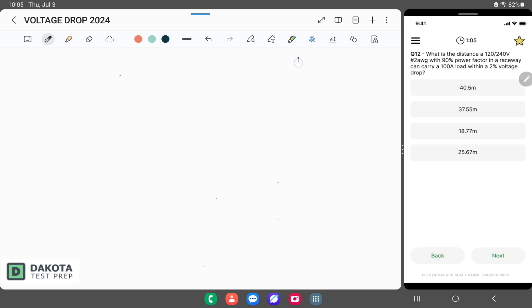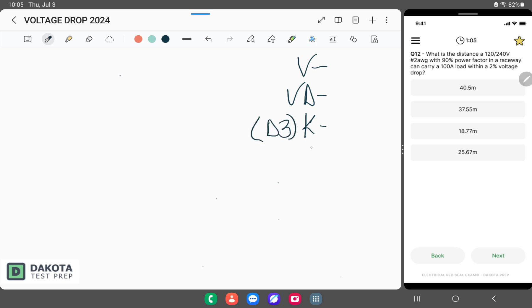So we have our voltage at the source. We have VD, which is our voltage drop in volts. We have our fancy new K factor, which is based off of table D3. We have an F factor as well — it's attached to D3. We have our I, which still means current. And we have L, which is length, and that has to be done in meters.